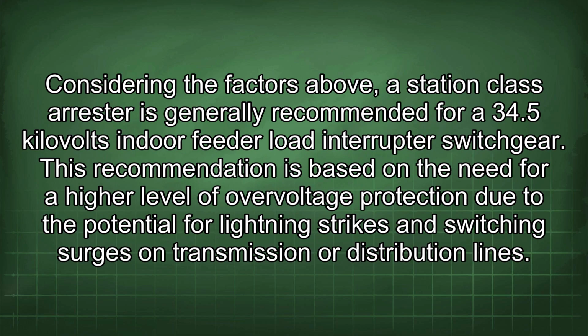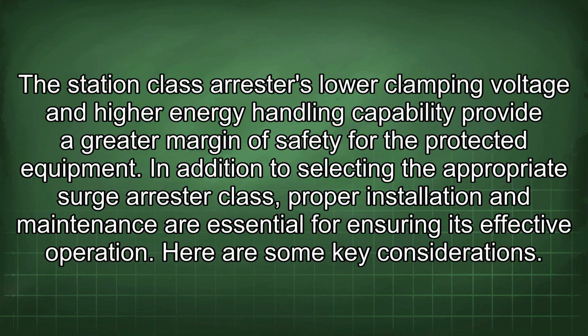Considering the factors above, a station class arrestor is generally recommended for 34.5 kV indoor feeder load interrupter switchgear. This recommendation is based on the need for a higher level of overvoltage protection due to the potential for lightning strikes and switching surges on transmission or distribution lines. The station class arrestors' lower clamping voltage and higher energy handling capability provide a greater margin of safety for the protected equipment.